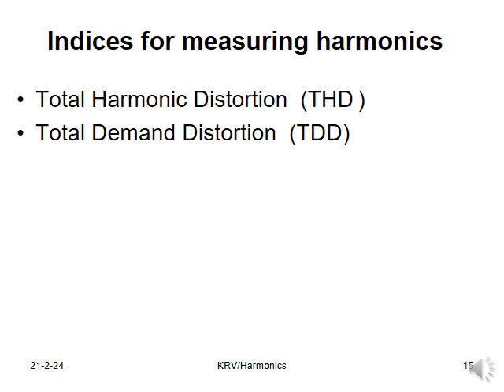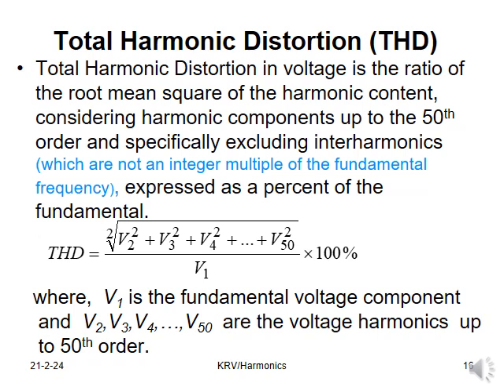Standards refer to two indices for measuring harmonics, namely total harmonic distortion, abbreviated as THD, and total demand distortion, TDD. Total harmonic distortion in voltage is the ratio of the root mean square of the harmonic content considering harmonic components up to the 50th order and specifically excluding interharmonics, expressed as a percentage of the fundamental. THD is equal to square root of V2 square plus V3 square plus V4 square etc. up to V50 square, divided by V1, into 100%, where V1 is the fundamental voltage component and V2, V3, V4 up to V50 are the voltage harmonics up to 50th order.